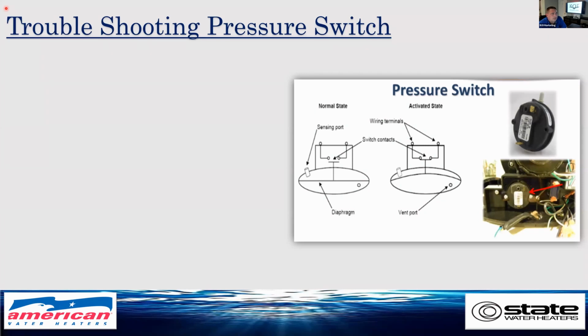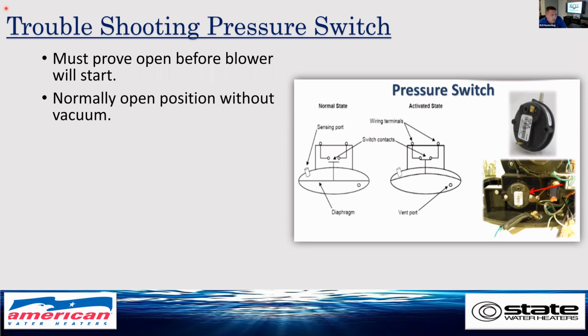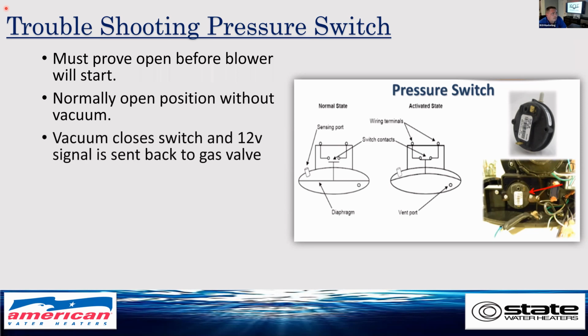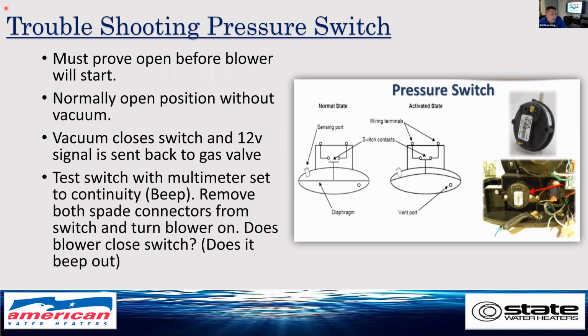Troubleshooting pressure switches. It must prove open before the blower will start, meaning that you cannot bypass this switch. The gas control has to see that it's open before it's closed. It's normally in the open position without vacuum. The vacuum closes the switch and a 12-volt signal is sent back to the gas valve. To test the switch with the multimeter set to continuity, remove both spade connectors from the switch and turn the blower on. Does the blower close the switch?